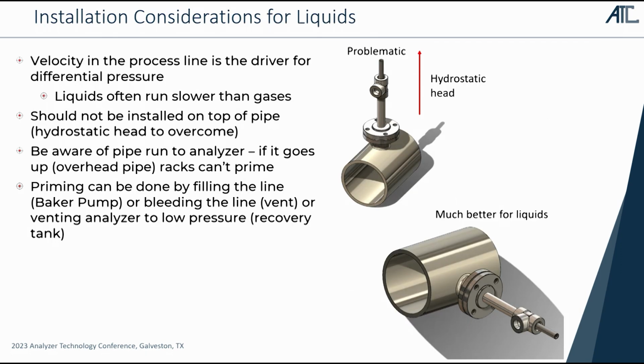So when we do the installations for liquids, our ideal installation is to sample off the side of the pipe and ideally have the analyzer be lower down, or the composite sampler, the grab sampler, whatever it is. Otherwise, we're going to have to consider how we're going to get that thing to prime. Once it starts to flow, it's a siphon and it just keeps on going. But we may have to add a mechanism for priming if we're going to try to run uphill.